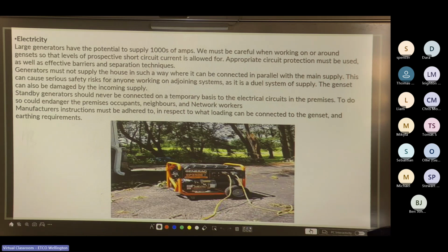Oh yeah, nice, with a changeover switch. Yeah. Some people in New Zealand, and more commonly over in America, will install a special socket outlet to hook up a small temporary generator, but they have to install a transfer switch or some kind of transfer system, so they don't have the mains connected at the same time the generator's running. Like if the power's out because of a storm, you can flick the transfer switch, plug in the generator, start it up, and it'll power your house. You just have to make sure you only turn on the loads that it can actually handle.